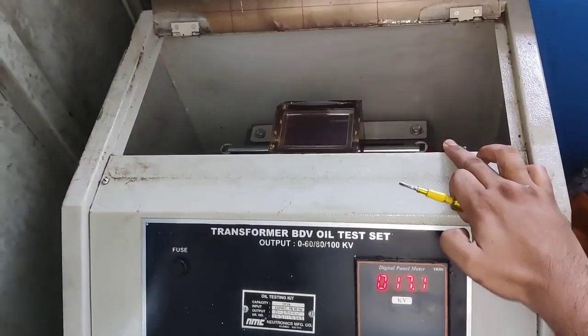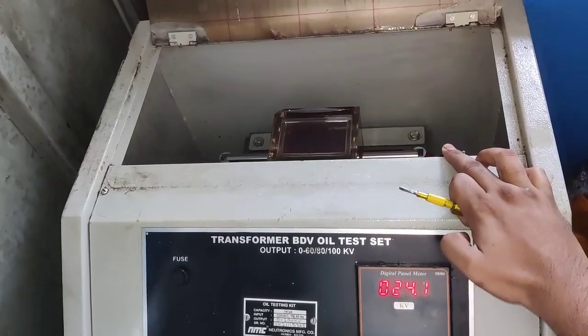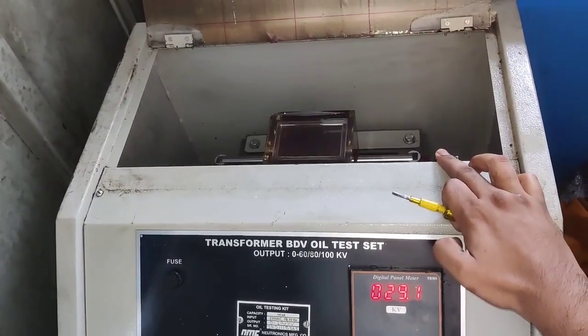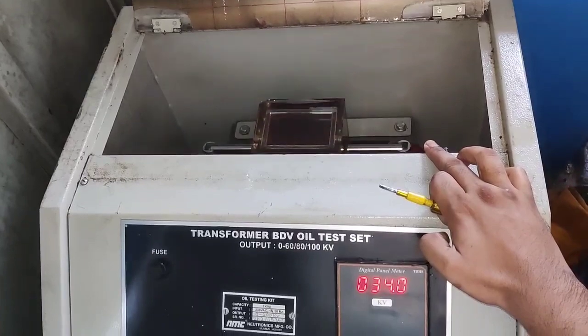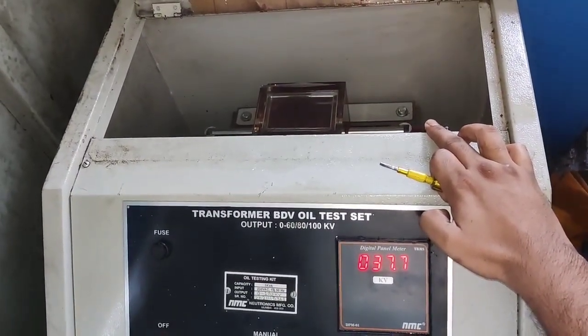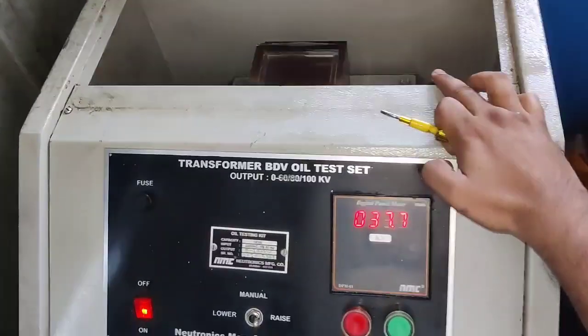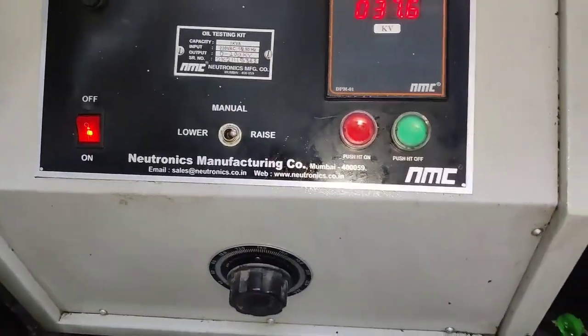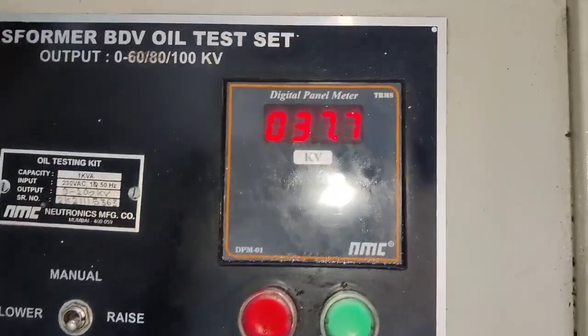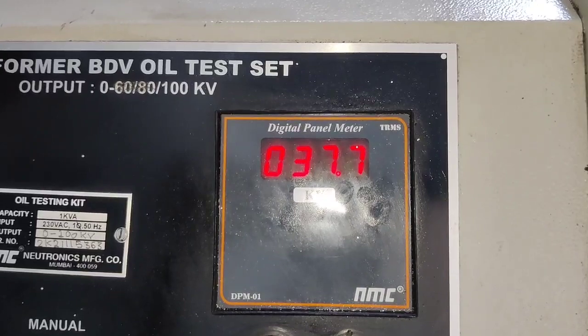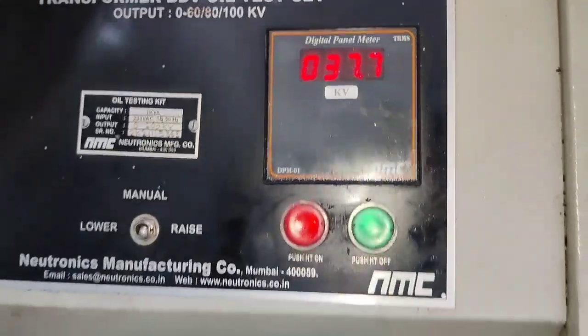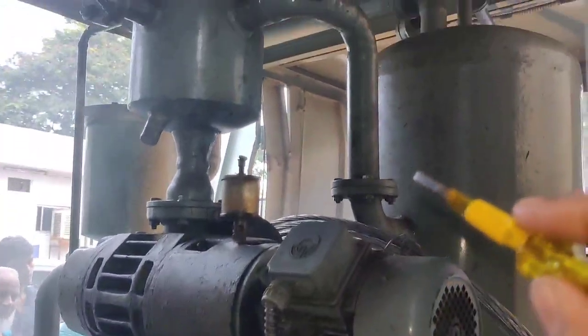You can see here, when we have a spark in this transformer oil, yes, we have a spark at 37 kilovolt. That means this transformer oil's BDV value, or breakdown voltage value, is 37. When a spark comes, the kilovolt meter value will hold. So you can read that this transformer oil's BDV value is 37.